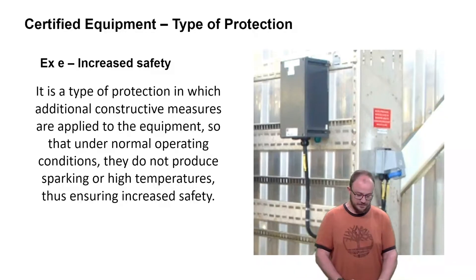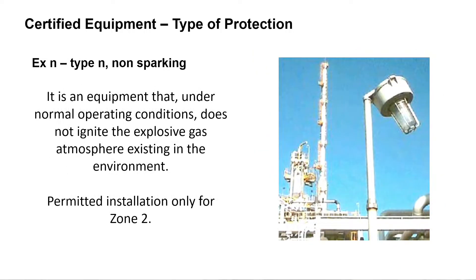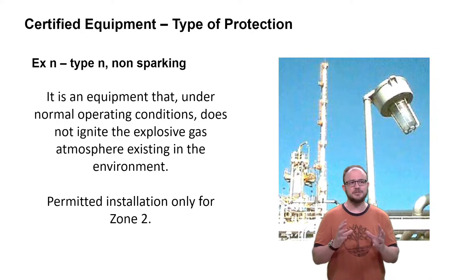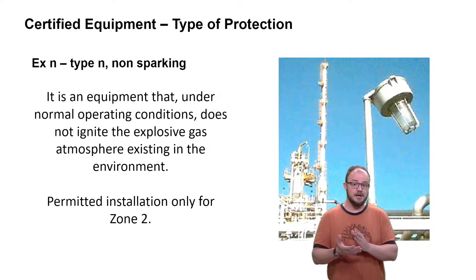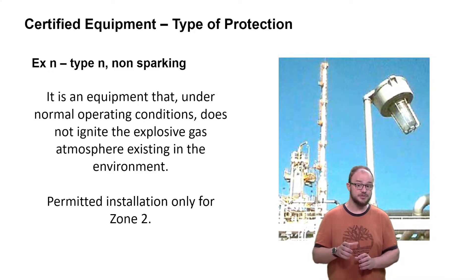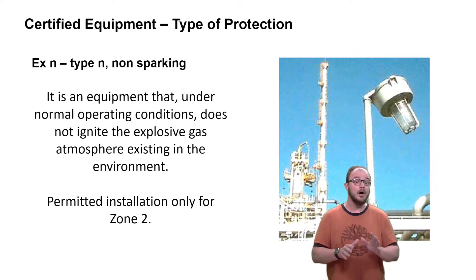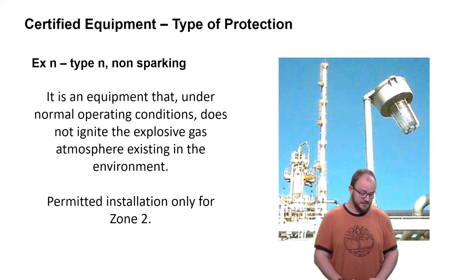We also have Type N — it's non-sparking. It's equipment with construction characteristics that permits installation only in Zone 2. Remember from the first class, we have Zone 0, Zone 1, and Zone 2. Only in Zone 2 can this equipment be installed.